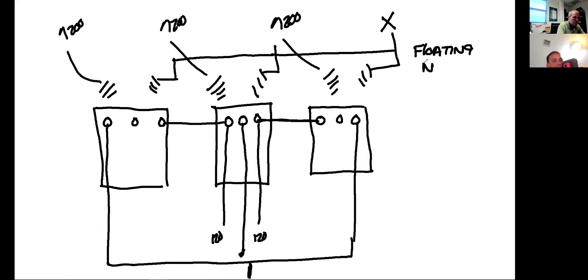So real quick, all I had to do here was add the extra transformer on this left-hand side and tie these two conductors together on the outside of each transformer. Now I've got 1, 2, there's my third phase down here at the bottom, and neutral. I made a closed delta bank just by adding a transformer. Now, as far as your drawings are concerned, you can take a closed delta bank and just flip it the other direction and take one transformer away.